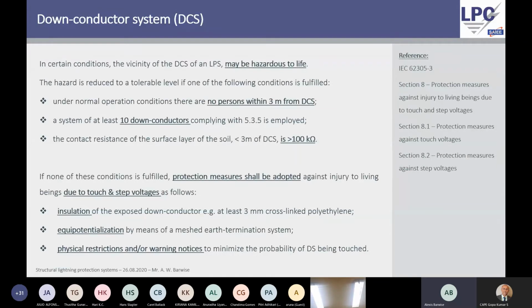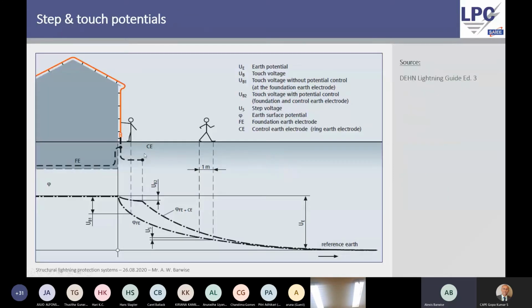And finally, the contact resistance of the surface layer within the 3 meter vicinity of the down conductors is above 100 kilo ohms. So that is saying, here where this human being is standing, we need to try and ensure that he's almost not connected to earth. That's the idea, so that there could not be a potential difference.